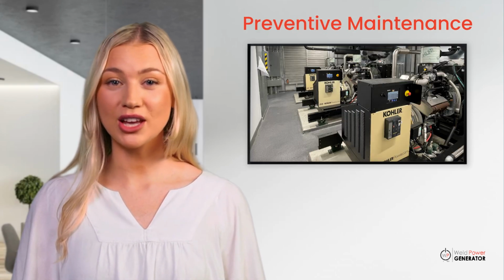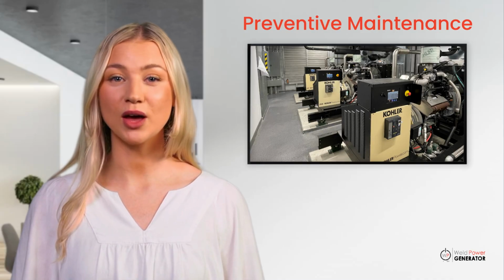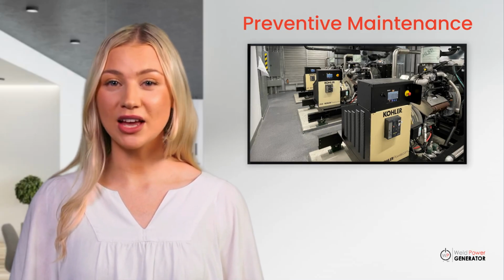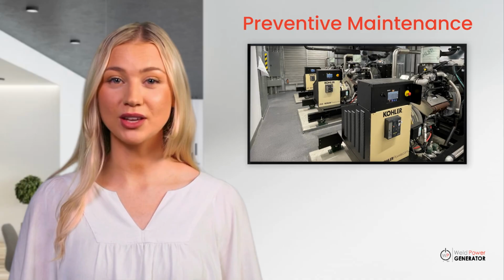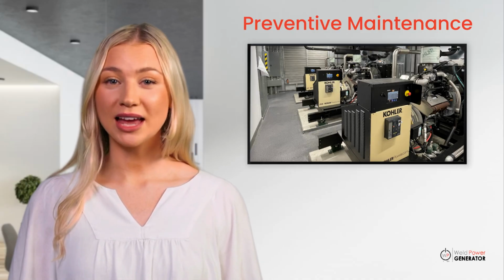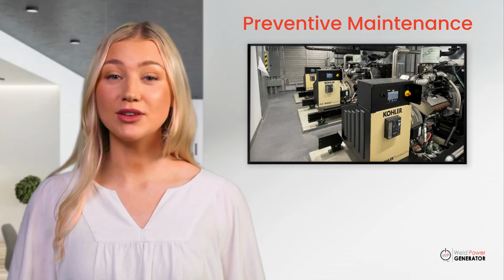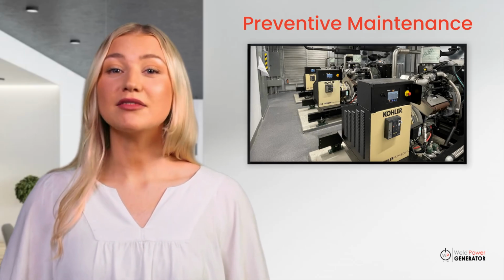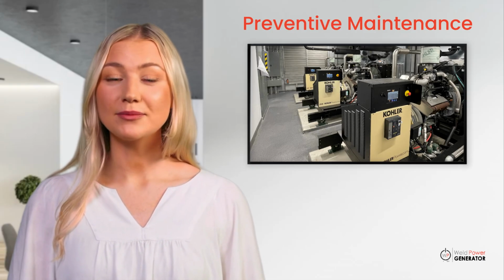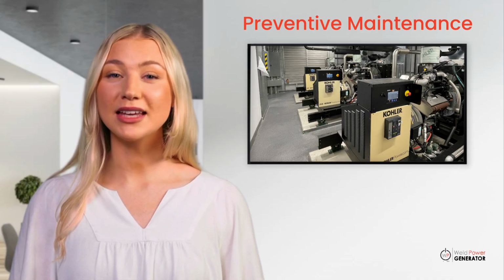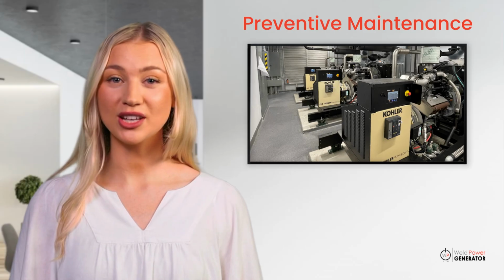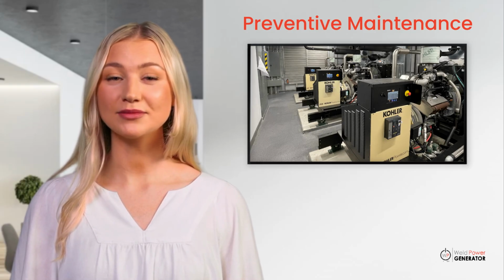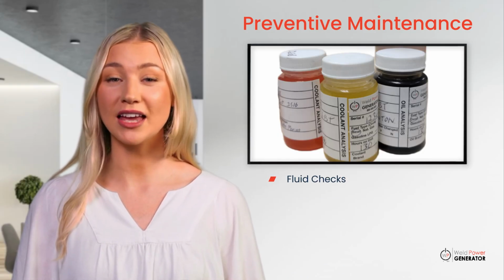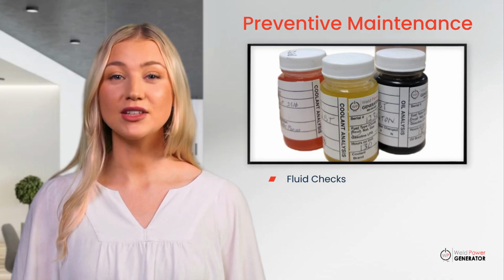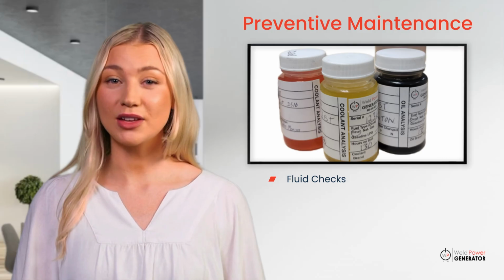The most expensive generator repairs are almost always the ones that could have been caught at a routine inspection. A frayed belt, a coolant leak, a battery showing low cranking amps, these are minor issues that announce themselves well in advance of failure, if someone is looking. A comprehensive preventative maintenance (PM) program for a commercial generator should include fluid checks. Engine oil, coolant, and fuel analysis can identify internal issues before they lead to system failure.